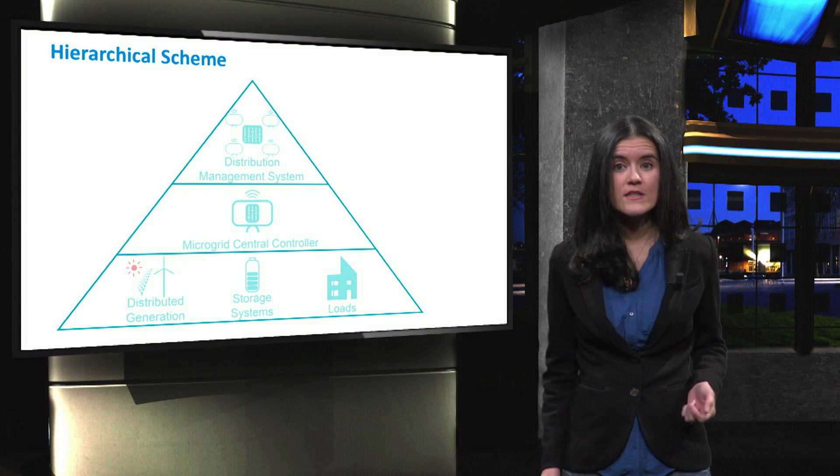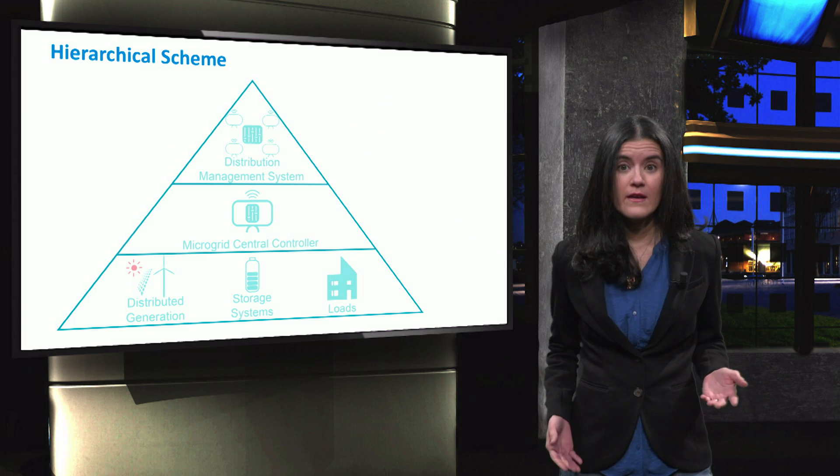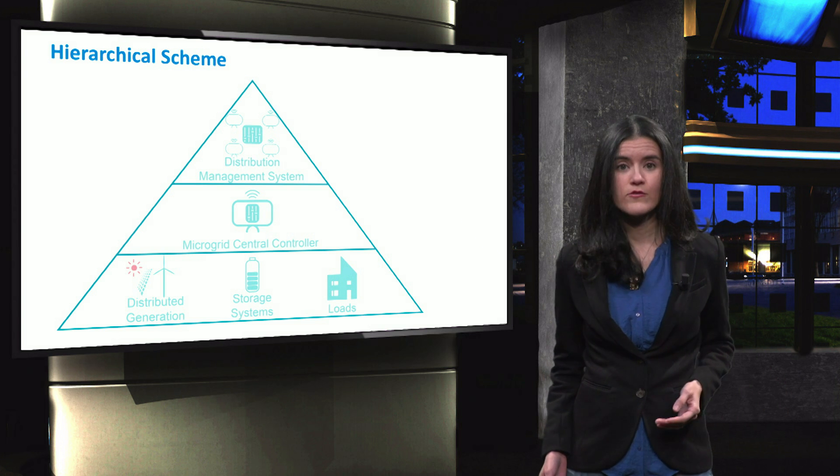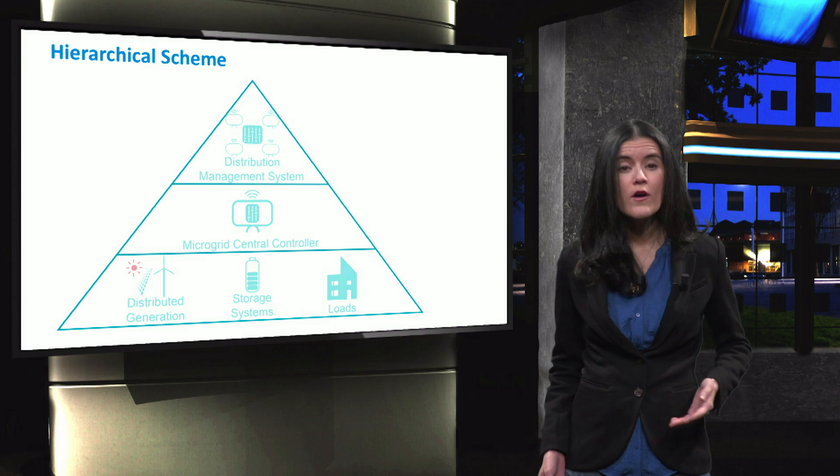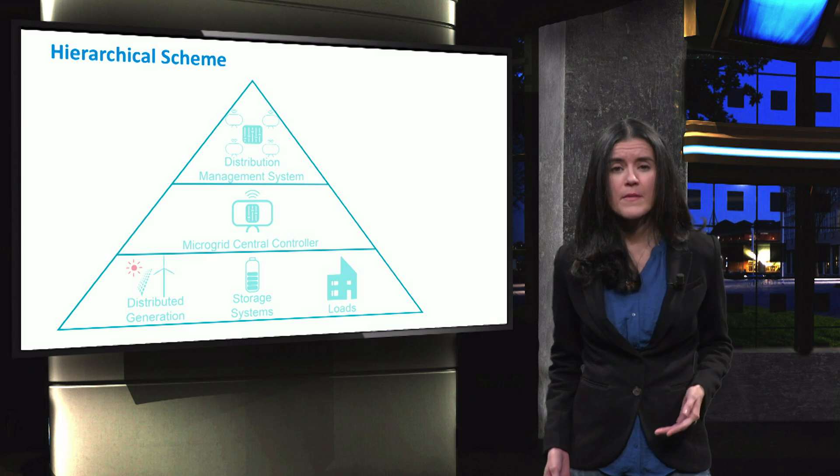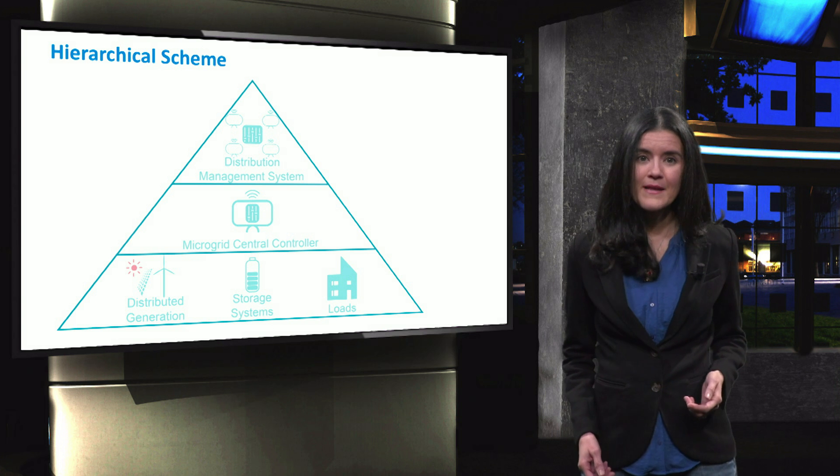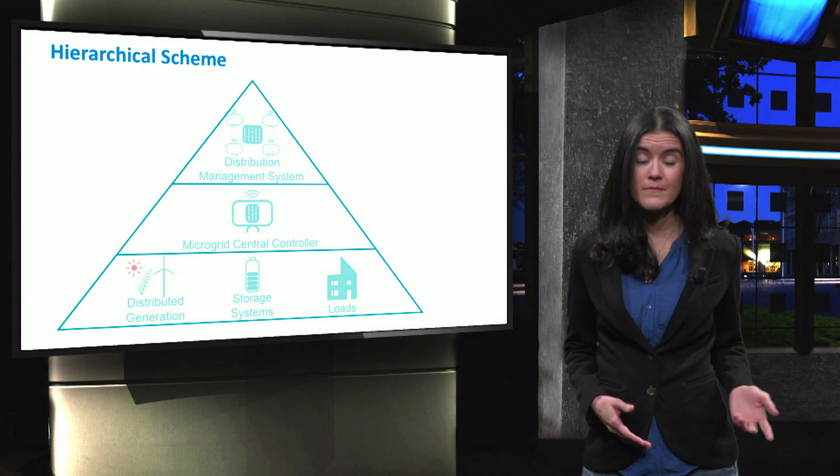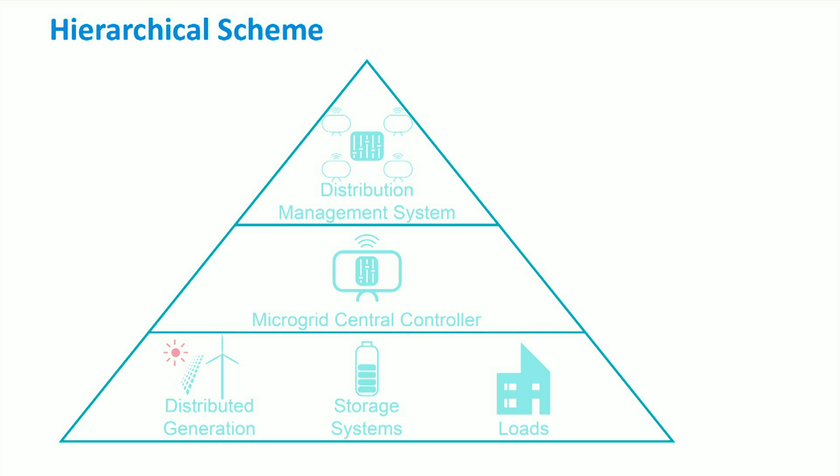We have seen that traditional control is hierarchical and it is divided into primary, secondary and tertiary control. A hierarchical control can also be implemented in microgrids, however, with some differences. Let's start describing it from the bottom. At the lowest level, where distributed generation, storage and loads are present, local control is responsible for the inner loop, outer loops and the implementation of droop control. This type of control is implemented in the power converters that interface the different components to the distribution grid.